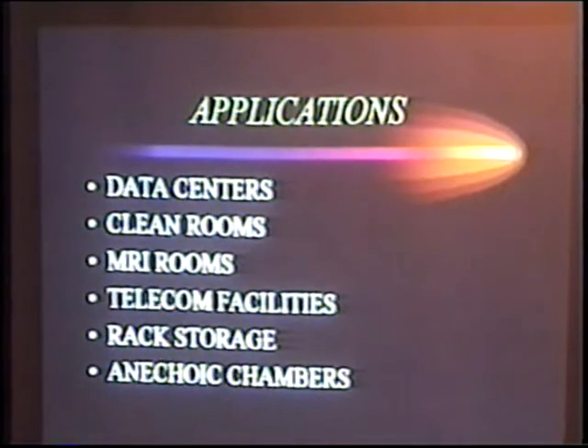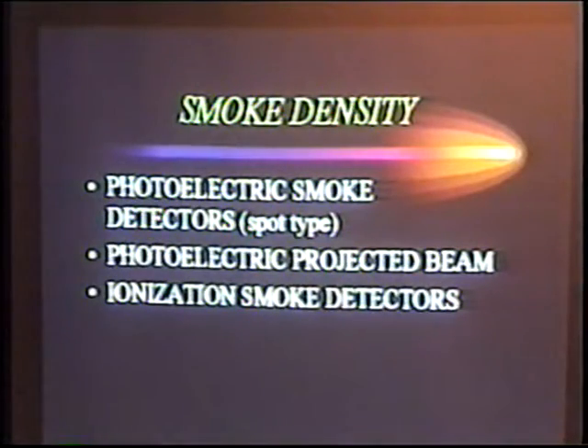Keep in mind, it's just the very first stage of fire. There's no smoke, there's no heat, there's no flame, it's just invisible particles. Moving right along, the second stage of a fire would be smoke density.